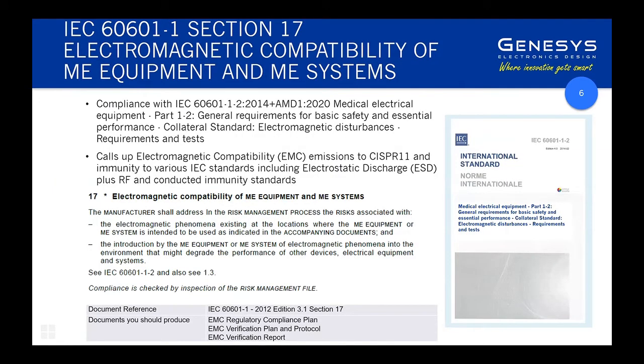IEC 60601-1 Section 17 calls up collateral standard 60601-1-2. The specific clause in Section 17 explains why we are doing this — 60601-1 is a recipe book that calls up all the ingredients in the form of other standards addressing specific aspects. The core standard called up is CISPR 11, one of the CISPR standards for electromagnetic compatibility covering radiated radio waves. There is also a standard specifically for electrostatic discharge and a suite of standards for immunity.